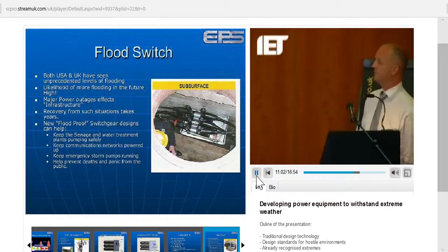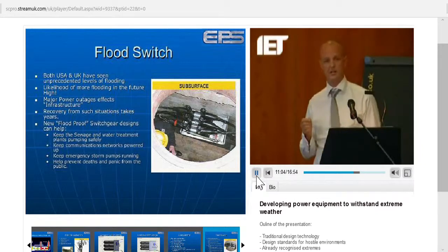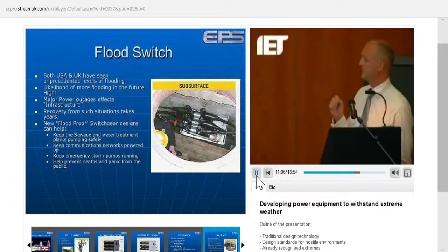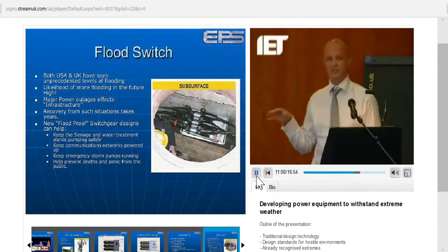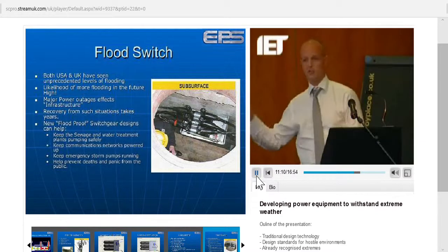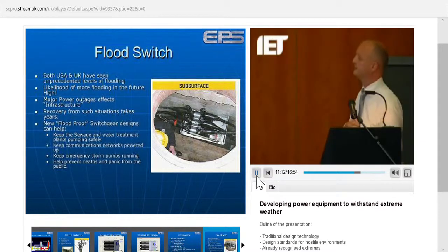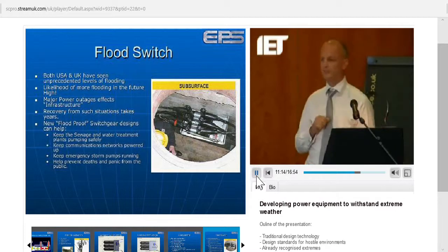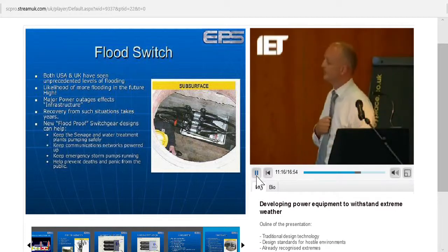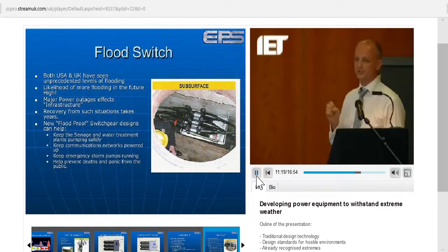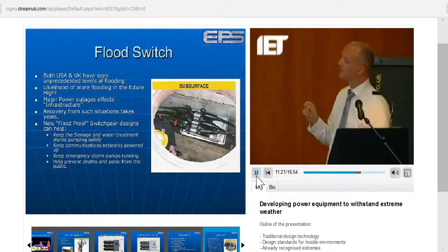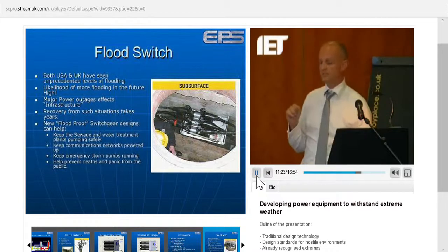The other big advantage of having the insulated outside of this type of switch is that there is no dielectric stress over the switch itself. It's all compacted, which makes it suitable for flooding. The device we've got at the moment can sustain its electrical integrity to a depth of about 3 meters.